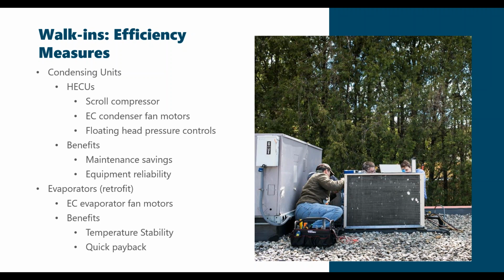So in kind of no particular order, we're going to talk about these condensing units, and what we're seeing is high efficiency condensing units, and these are being rolled out at the manufacturer level. So it's something that we're really trying to promote, and within that kind of package system, you have a scroll compressor, and sometimes for some of the larger units, we're now seeing discus compressors as well. So the scroll and discus are the hermetic and semi-hermetic efficient compressor varieties. And then with that, we're seeing variable speed condenser fan motors that then allow us to float that head pressure. So dropping the saturated condensing temperature when outdoor air temperatures allow it to still reject heat.